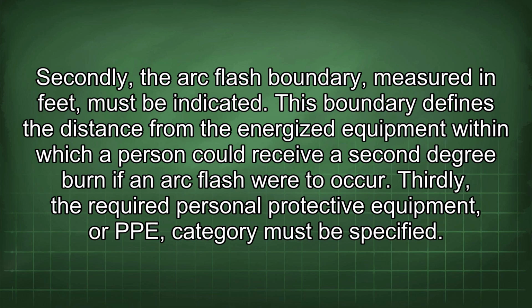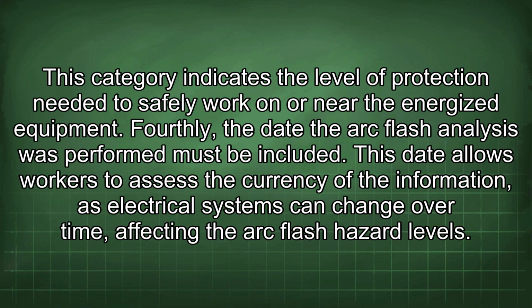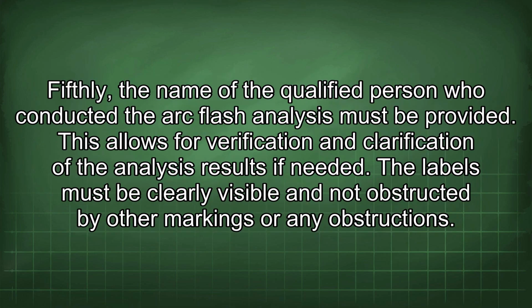Thirdly, the required personal protective equipment, or PPE category, must be specified. This category indicates the level of protection needed to safely work on or near the energized equipment. Fourthly, the date the arc flash analysis was performed must be included. This date allows workers to assess the currency of the information, as electrical systems can change over time, affecting the arc flash hazard levels. Fifthly, the name of the qualified person who conducted the arc flash analysis must be provided. This allows for verification and clarification of the analysis results if needed.